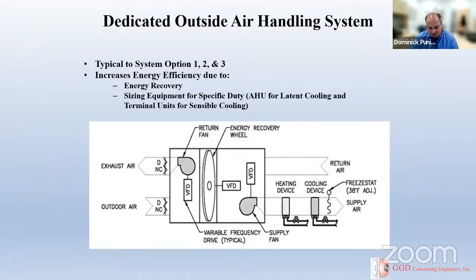So all these options, as I was mentioning, the code is really pushing for separating the ventilation system from your additional space heating and cooling. And when we're designing ventilation systems, we use what's called a DOAS, a dedicated outdoor air handling system, and that's designed to temper your ventilation. It's a very efficient approach because it's going to incorporate energy recovery. So all that ventilation air is going to either be, depending upon the season, preheated or pre-cooled by this energy recovery. What happens is that return air that we've spent good money to temper gets passed through the energy wheel. That energy media transfers that energy to the incoming outdoor air, which is then heated in the heating season, pre-cooled in the summertime. And then from there, we provide any additional heating and cooling.